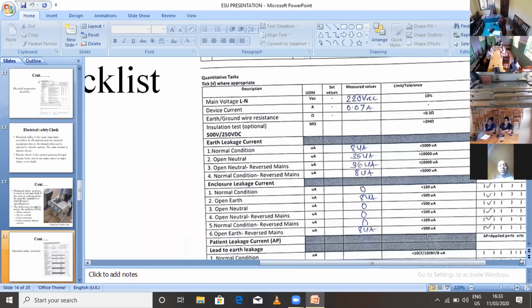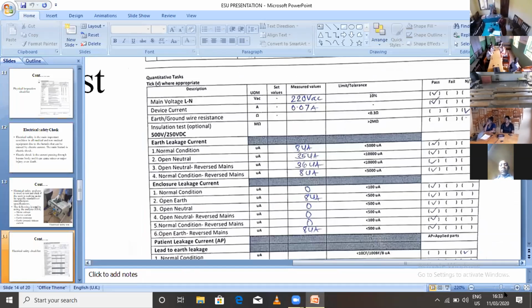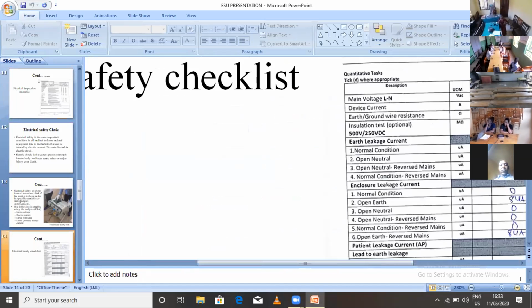You can see the checklist for electrical safety. It shows main voltage of 200, device current, ground wire, insulation test, enclosure leakage currents, patient leakage current. Everything is there. This is the checklist we use to test for electrical safety.